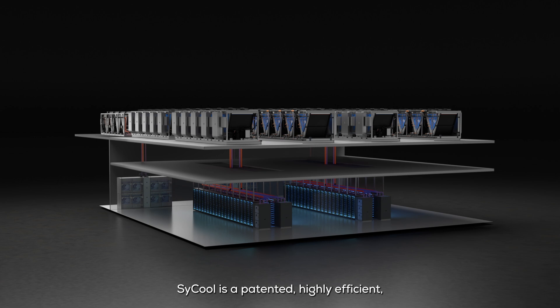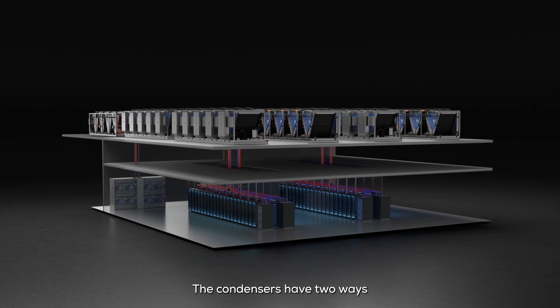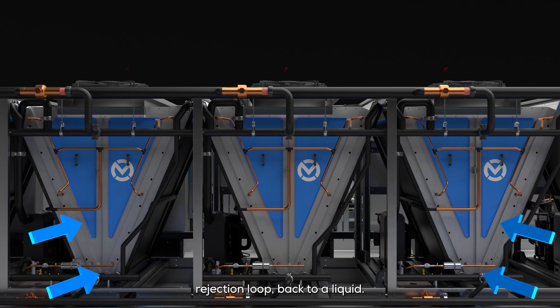SyCool is a patented, highly efficient, waterless data center heat rejection solution. The condensers have two ways to convert the vapor heat transfer coolant within the pump-assisted thermosyphon heat rejection loop back to a liquid.